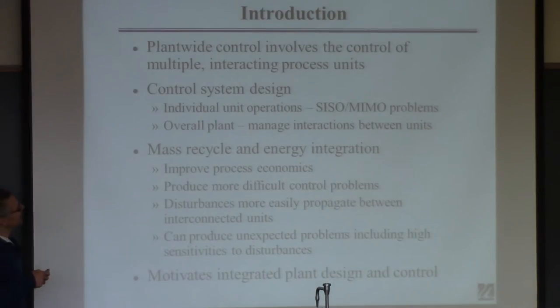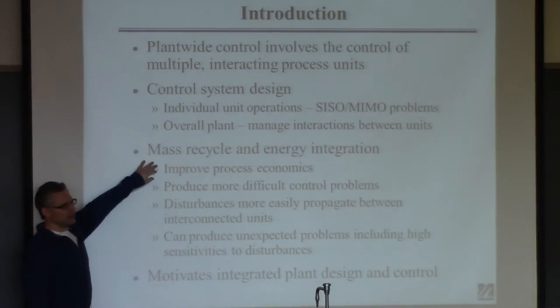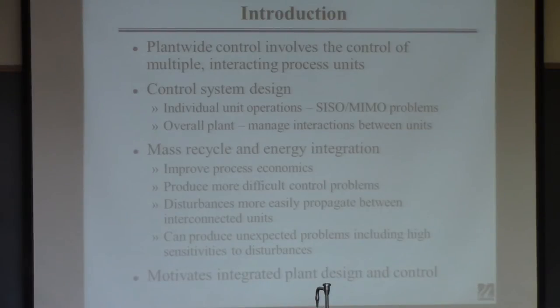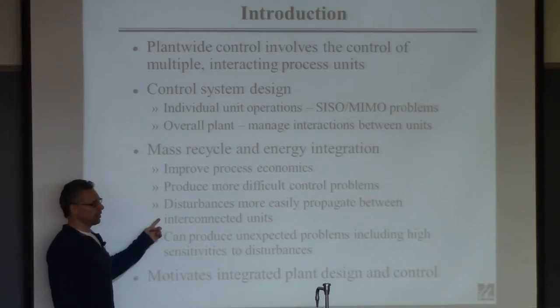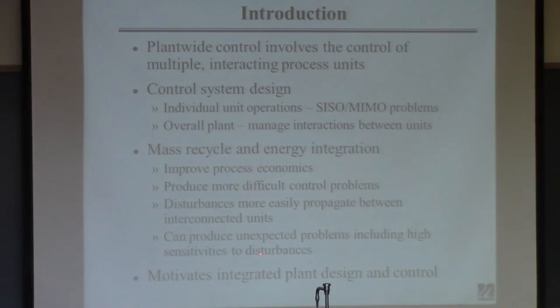What distinguishes plant-wide control is that unit operations are integrated together, usually through recycle of mass and energy. You do heat exchanger networks in process design because it saves money — it's great from a steady-state economic perspective. But it produces much more difficult control problems, because a disturbance in one unit can propagate to a disturbance in another unit.